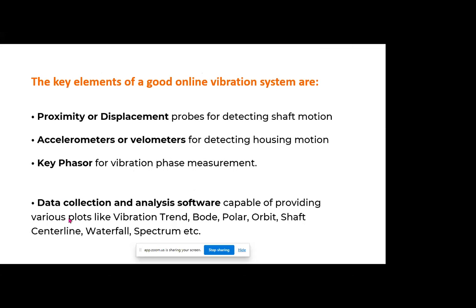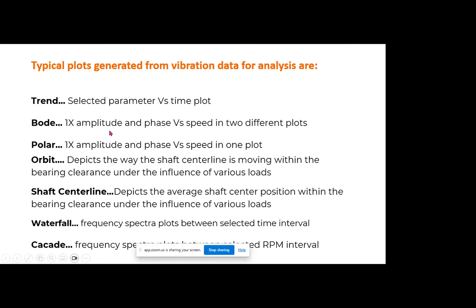When looking at a turbomachinery vibration monitoring system, the key elements of a good system are proximity probes — displacement probes for detecting shaft movement — acceleration or velocity sensors for detecting housing motion, and essentially a key phaser, which is a very important input for vibration phase measurement. Apart from that, we need good software capable of providing various data plots to diagnose machinery problems like bode, polar, orbit, shaft centerline, and more.